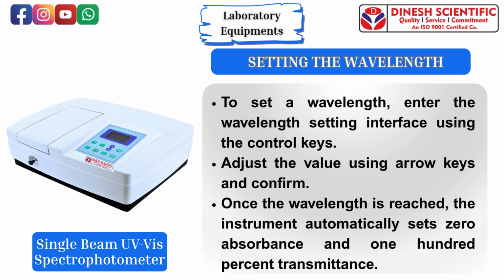Setting the wavelength. To set a wavelength, enter the wavelength setting interface using the control keys. Adjust the value using arrow keys and confirm. Once the wavelength is reached, the instrument automatically sets 0 absorbance and 100% transmittance.